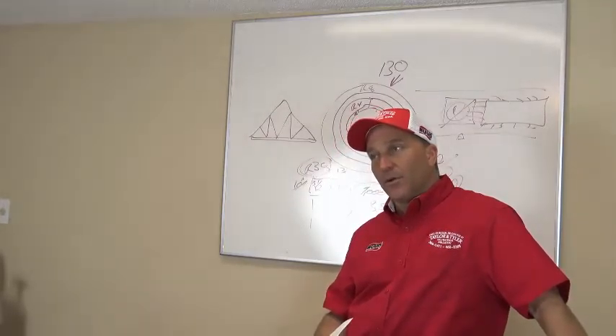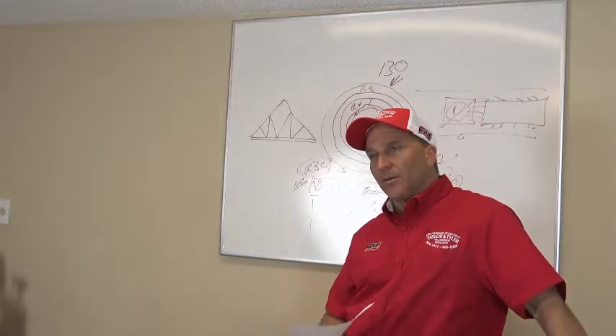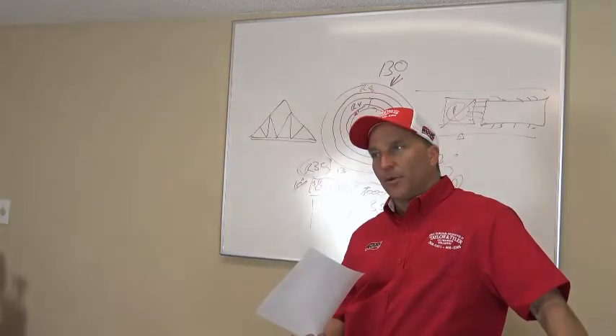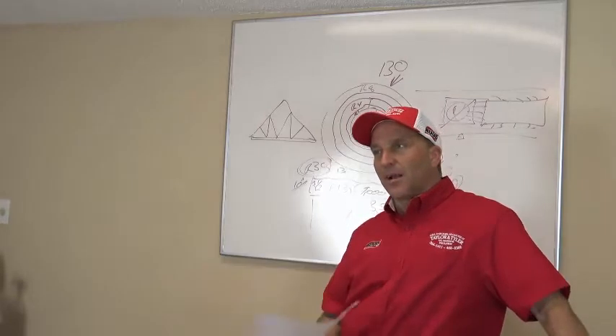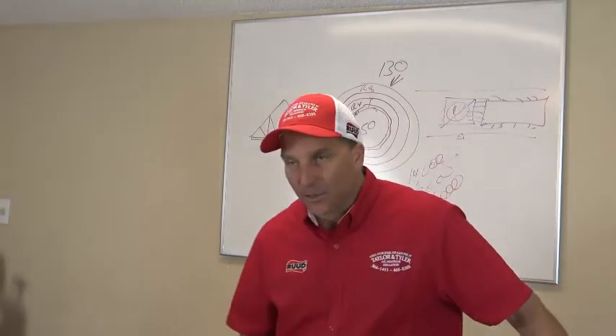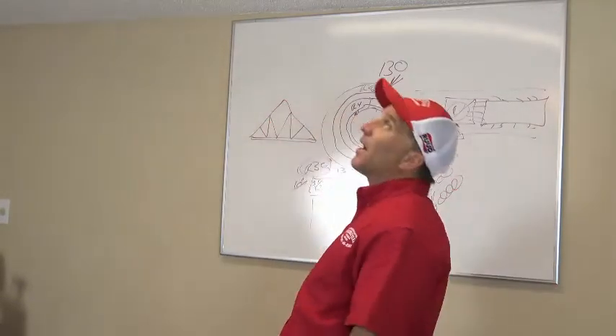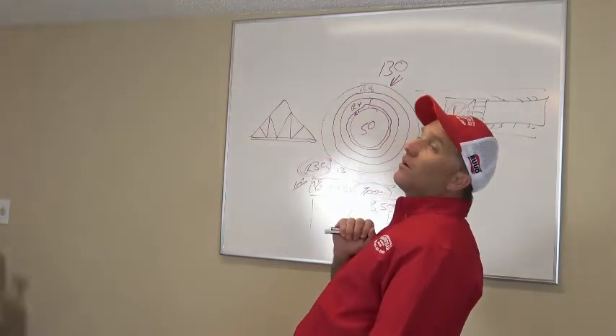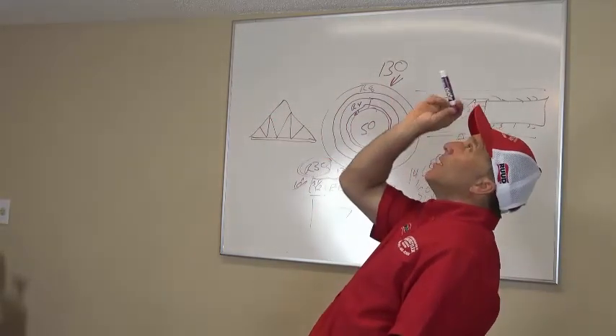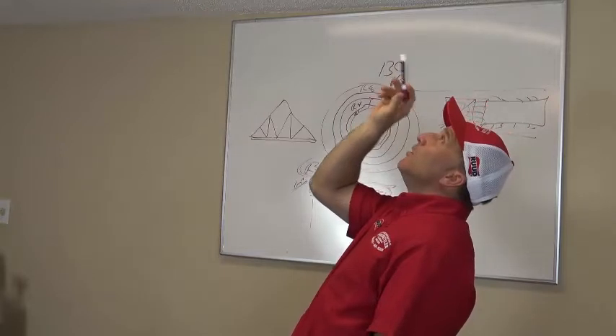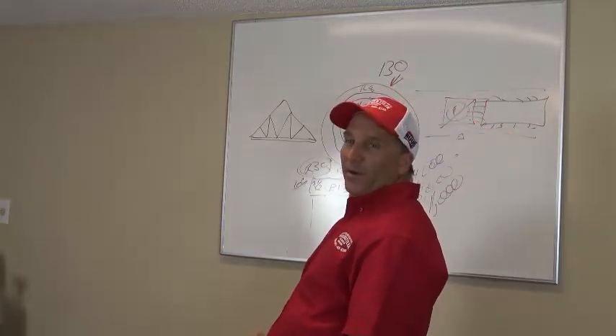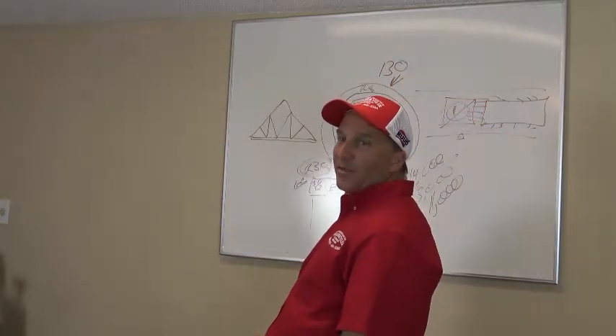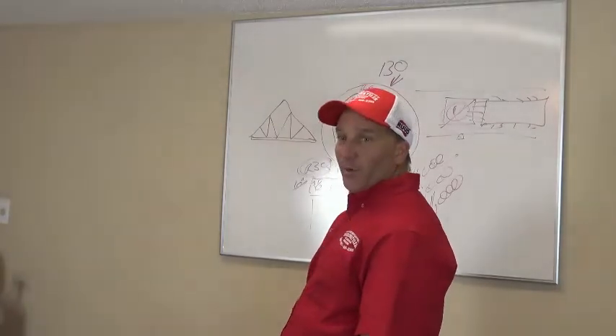Okay. You got a vertical gas heat system and your blower wheel is dirty. I'm going to give you a little hint. Pull the blower wheel out. After you pull the blower wheel out and you vacuum the inside of that cabinet, literally get your whole body up inside there, upside down, take your drop light or your flashlight and shine straight up through the chambers, and you can see the evaporator coil up there, right? Now you can see if the coil's dirty or not. And I'm going to tell you, it's going to be dirty.